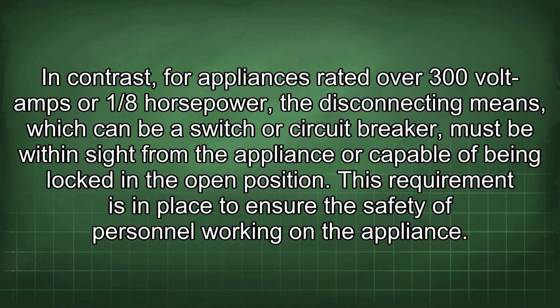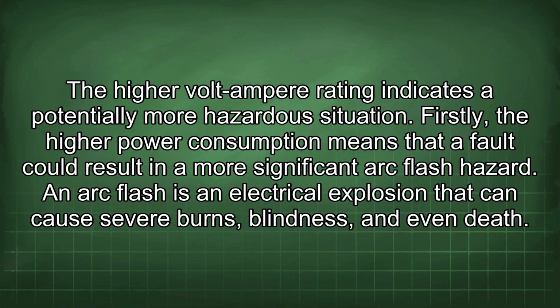In contrast, for appliances rated over 300 volt-amps or 1/8 horsepower, the disconnecting means, which can be a switch or circuit breaker, must be within sight from the appliance or capable of being locked in the open position. This requirement is in place to ensure the safety of personnel working on the appliance. The higher volt-ampere rating indicates a potentially more hazardous situation.